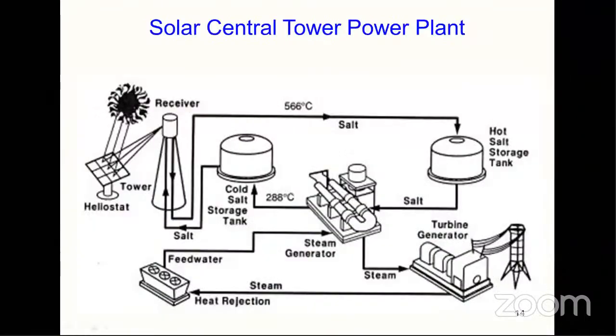The next technology is the solar central power tower, where higher concentration can be attained using heliostats that focus on the tower. But the temperatures are very high, as mentioned earlier, going up to 1500 to 2000 degrees Celsius. At such high temperatures, you cannot use water as a working fluid because of the possibility of dissociation of water. So in order to avoid that and maintain the cycle temperature, we generally go for molten salt.